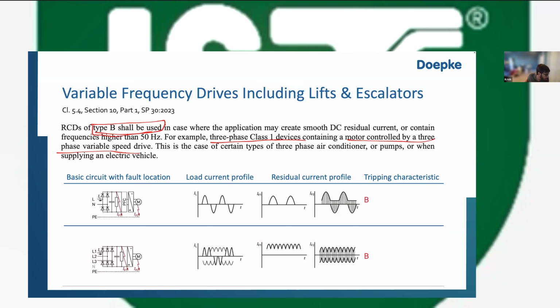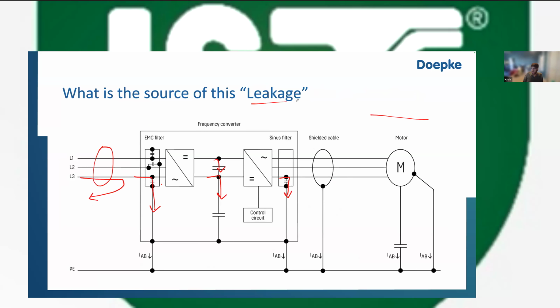Mr. Ravi, first of all, thank you for the valuable presentation. In case of regenerative type elevator drive applications like Otis, do we need to increase the tripping sensitivity? The first thing you need to figure out is, similar to the question asked before this, what is the leakage current in this drive under normal situations? When I have that data, if you tell me 5 to 15 kilowatt, I can tell you how much current that is. That is a very simple thing. But what sensitivity is required depends on how much leakage current this drive will create without a fault.